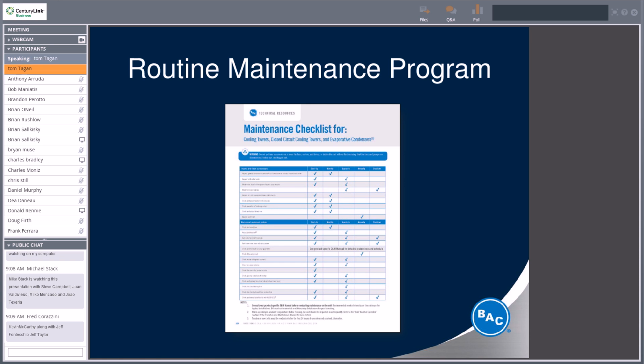A couple of other things, as you go down through the middle of this, you've got the mechanical equipment system. You want to check the belt condition. You want to check the belt tension. It talks about lubricating the fan shaft bearings, lubricate the motor base adjusting screw, check and lubricate if you have a gear or a direct drive motor. Check the drive alignment. Occasionally you want to check, they're saying quarterly, to check the motor voltage and current.